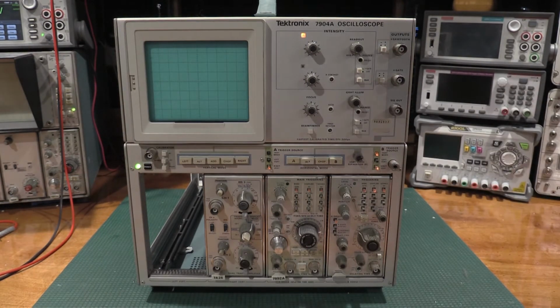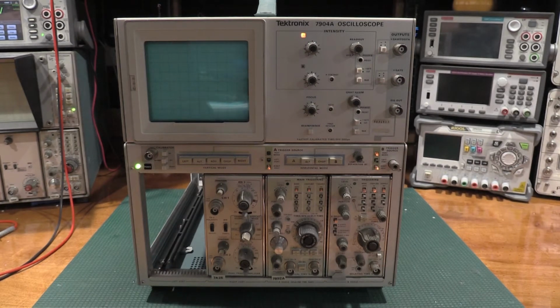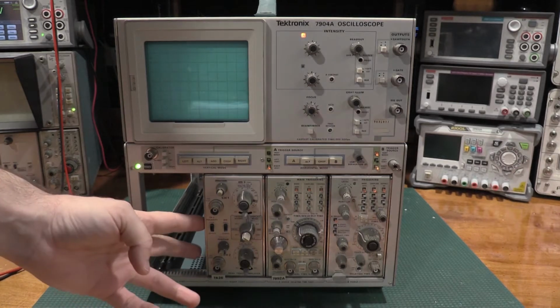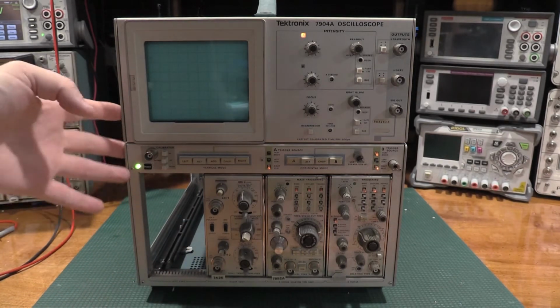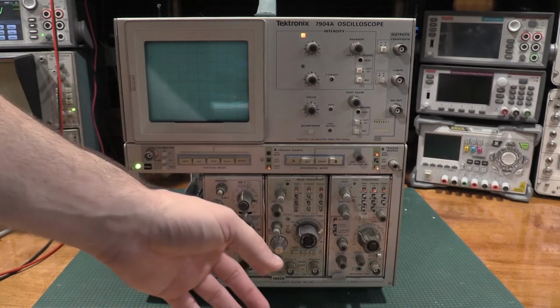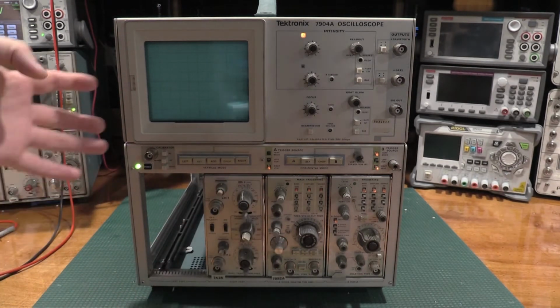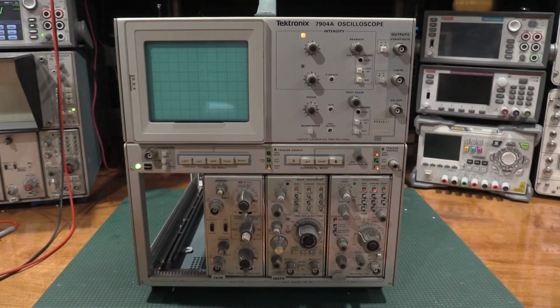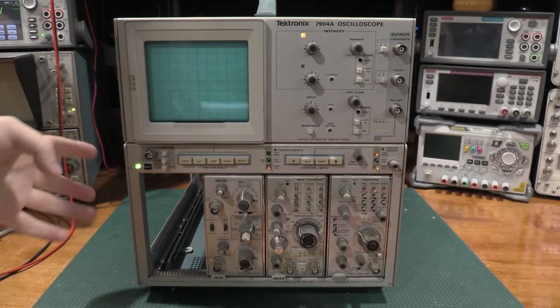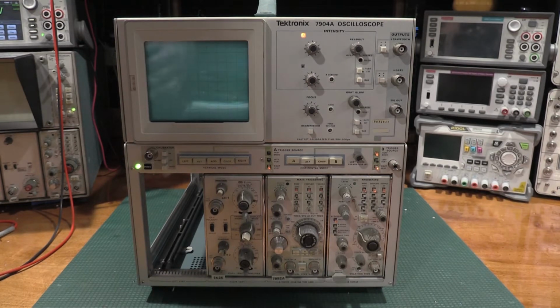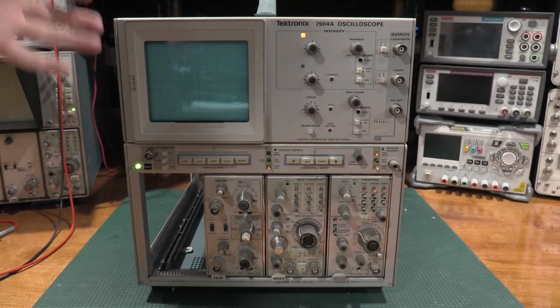So I've had most of the lab warming up now for about an hour and a half, 2 hours. I need to pull a service manual for the unit, and then we will go through the calibration on the frame. I won't be doing any of the calibrations of the plugins on this video, because to do a full calibration on one of these 7K frames, you have to calibrate the frame, then you have to calibrate the vertical, then you have to calibrate the time base, and that's 3 different calibrations and alignments. So this video will be just on the frame itself, which is primarily power supply. To put it into the 400 series terms that I used when I did the 465 calibration, it would be the power supply of the tube.